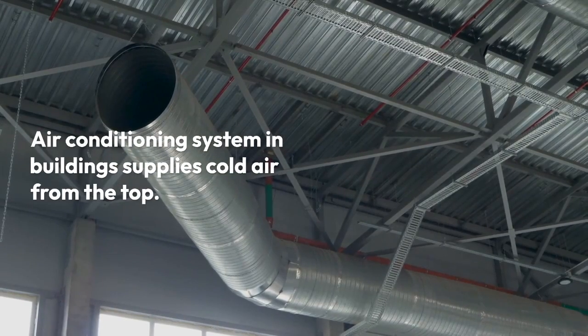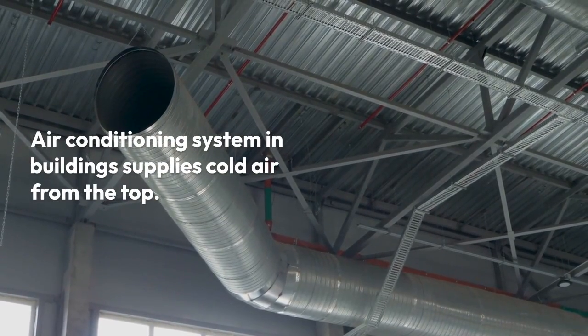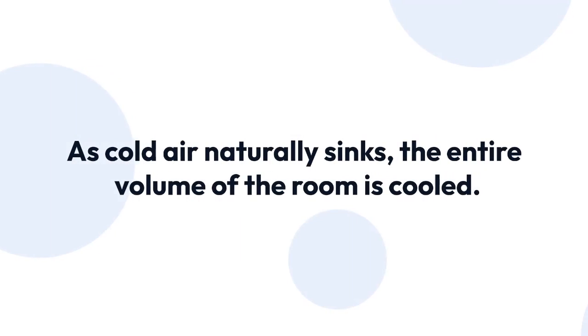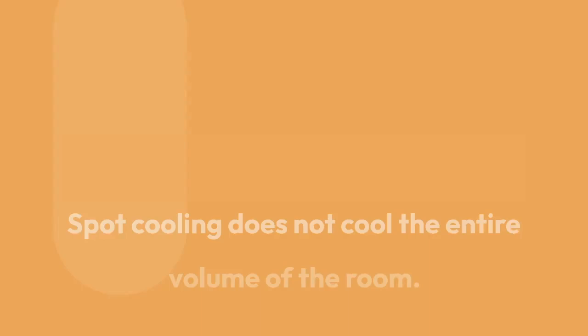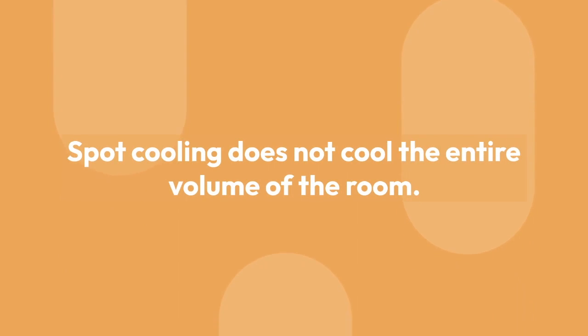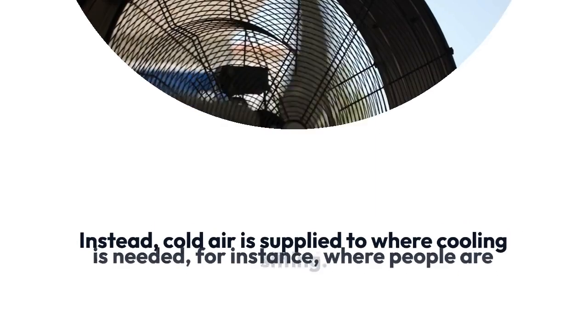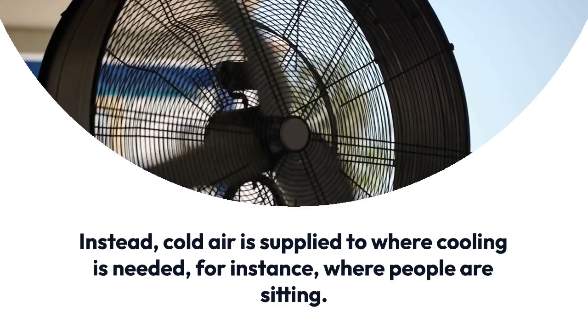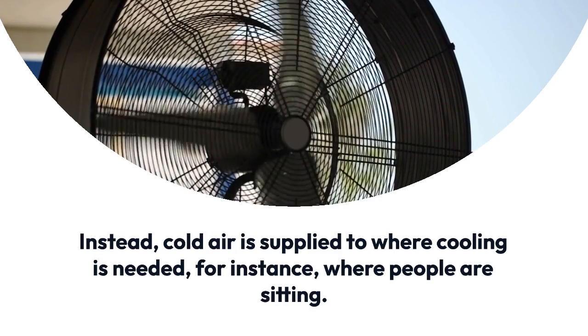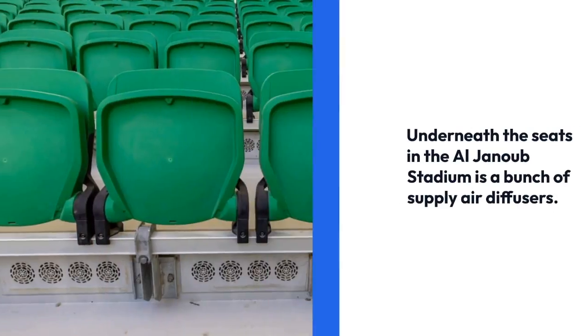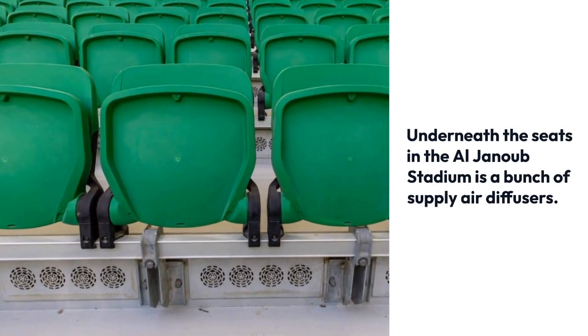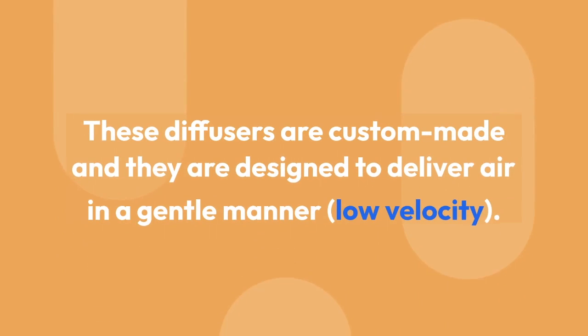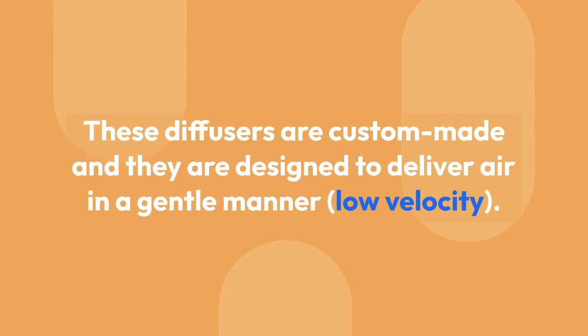Traditionally, the air conditioning system in buildings supplies cold air from the top. As cold air naturally sinks, the entire volume of the room is cooled. On the other hand, spot cooling does not cool the entire volume of the room. Instead, cold air is supplied to where cooling is needed, for instance, where people are sitting. Underneath the seats in the Al Janoub Stadium is a bunch of supply air diffusers. These diffusers are custom made, and they are designed to deliver air in a gentle manner.